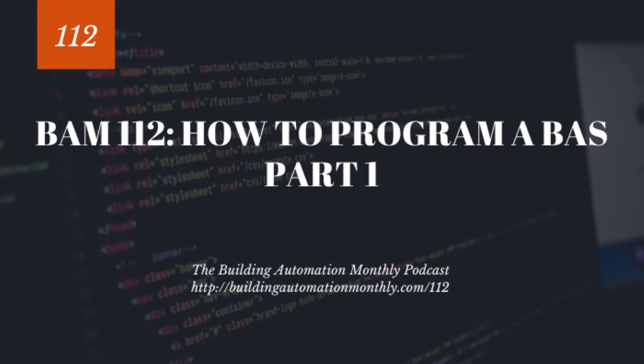Now, some folks will argue with me and they'll say, well, no, Phil, that's not true. A VAV box code is a VAV box code. But really, is it? Think about it. A VAV box code in a containment room is often going to be driven off the pressure in the room and the pressure outside the room, and you're going to be trying to control positive pressure in the exterior of the room if you're trying to contain things inside, and in the interior of the room if you're trying to contain things from coming inside.